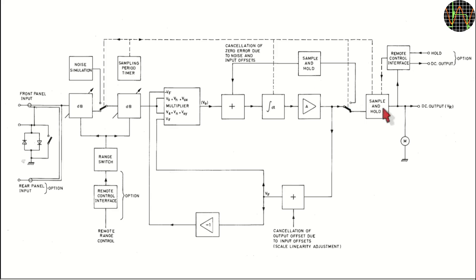Finally, during the 1ms of producing the auto offset, the meter and the DC output are disconnected from the signal processing, but the last value is kept by another sample-and-hold circuit to make the auto-zero adjustment process completely invisible.